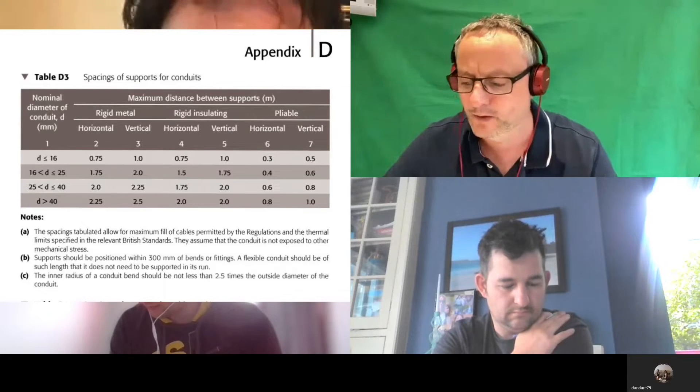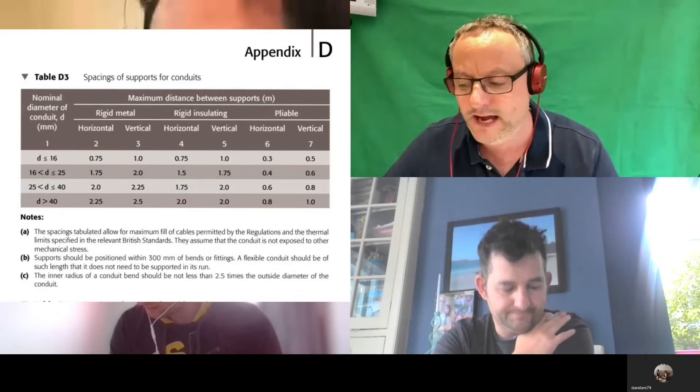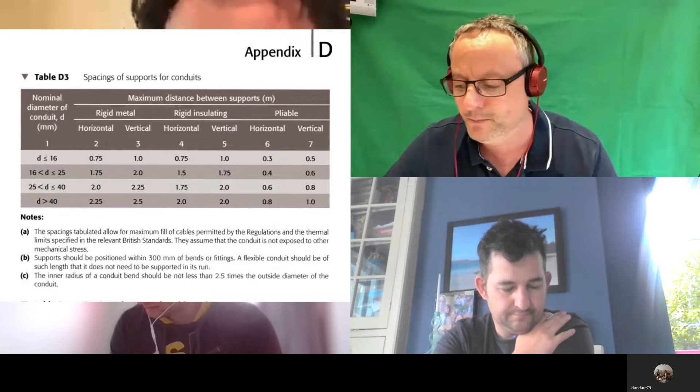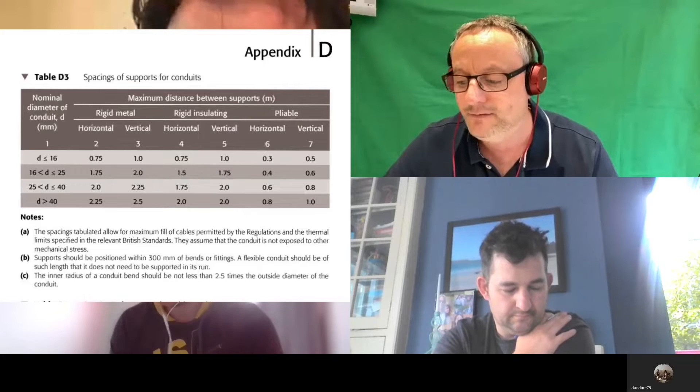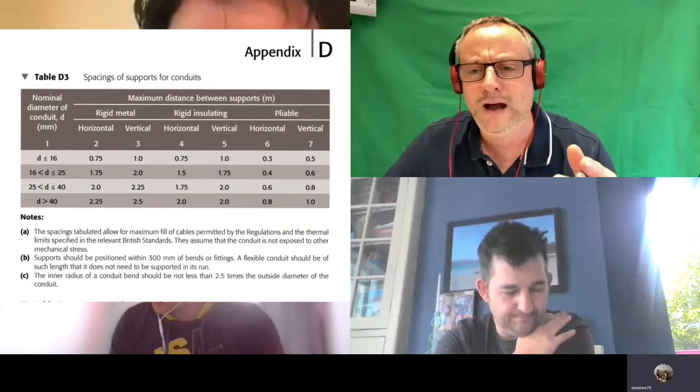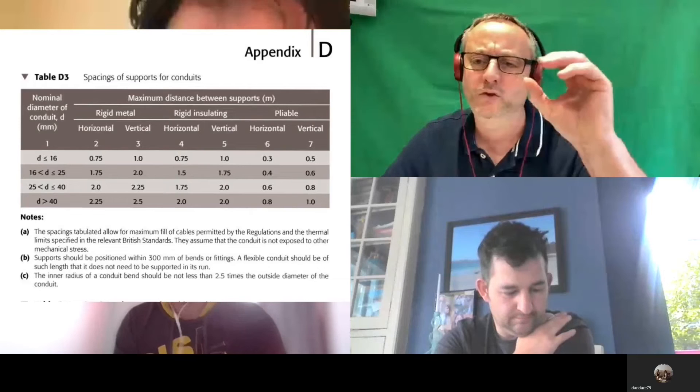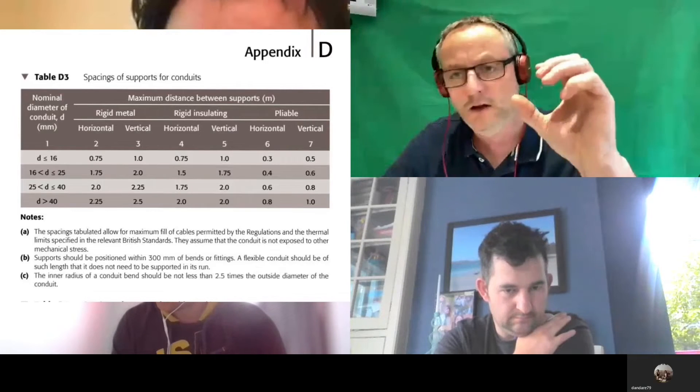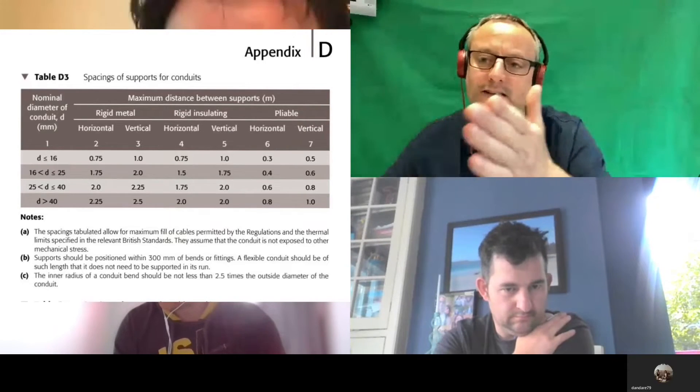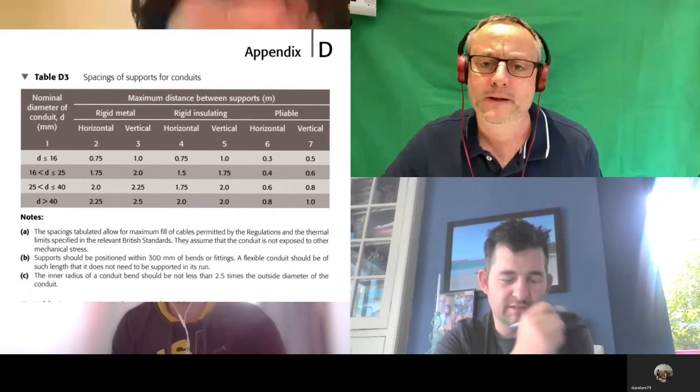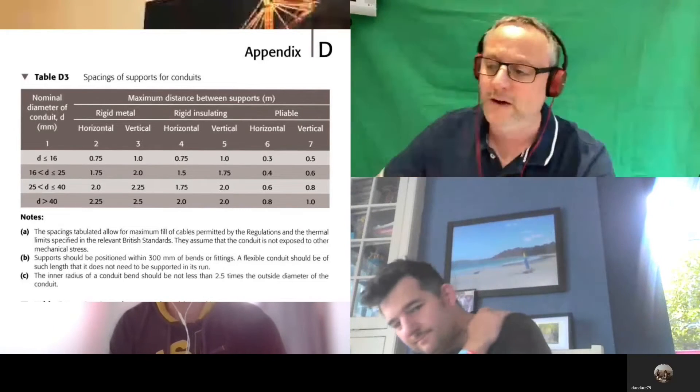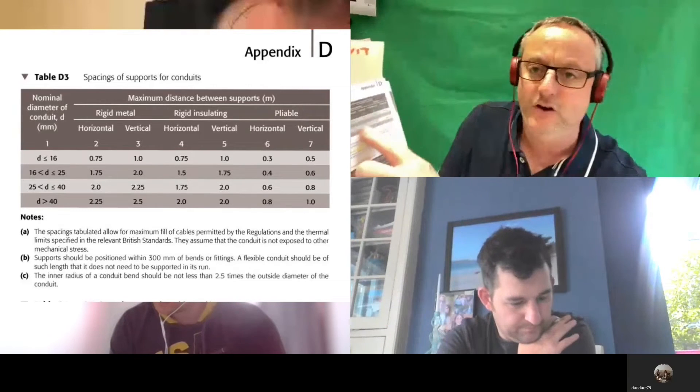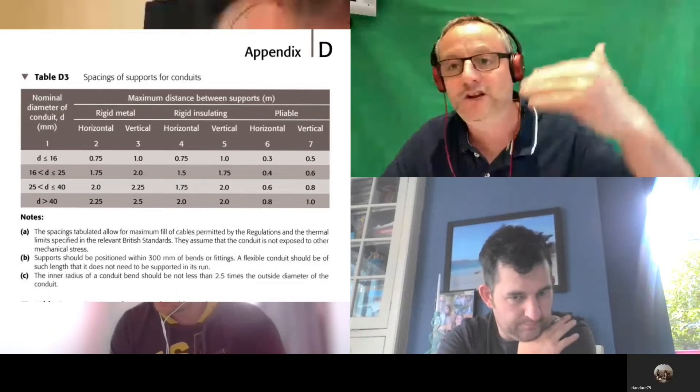1.75. Do we all see that? Up to and including—so greater than 16 but up to including 25 is 1.75, and vertically two meters. How is it that we've got now 25, not 16—considerably bigger conduit—yet our spacings can now be further apart? It's stronger.